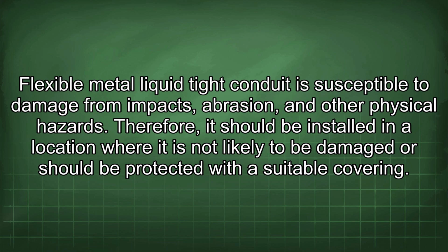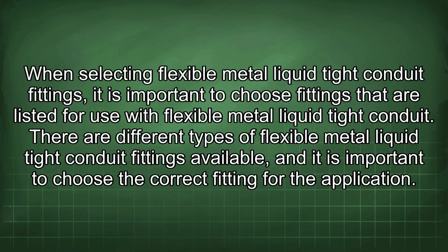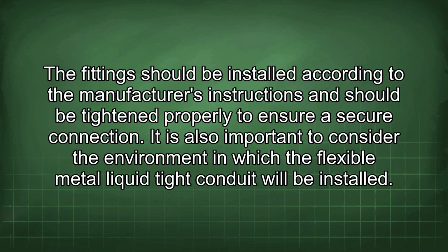Therefore, it should be installed in a location where it is not likely to be damaged or should be protected with a suitable covering. When selecting flexible metal liquid tight conduit fittings, it is important to choose fittings that are listed for use with flexible metal liquid tight conduit. There are different types of fittings available, and it is important to choose the correct fitting for the application.